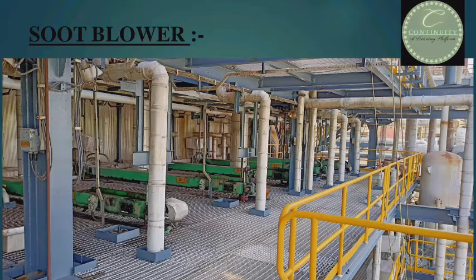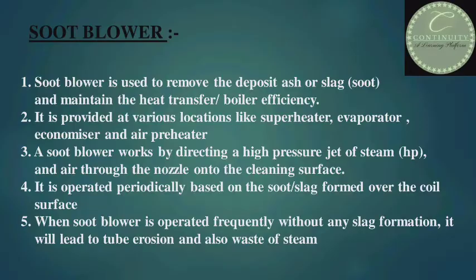What is a soot blower? Look at the figure. There are something in green color — this is the soot blower. Soot blower is used to remove the deposited ash or slag, which is also known as soot, and maintain the heat transfer or boiler efficiency. It is used at various locations like superheater, evaporator, economizer and air preheater. A soot blower works by directing a high-pressure jet of steam and air through the nozzle onto the cleaning surface. It is operated periodically based on the soot or slag formed over the coil surface.